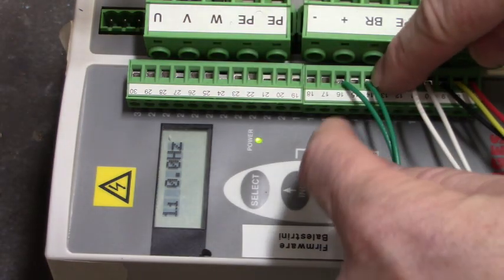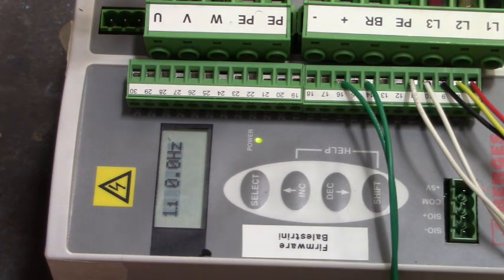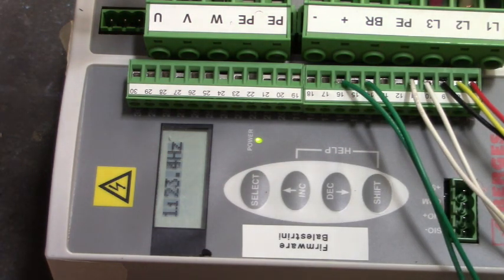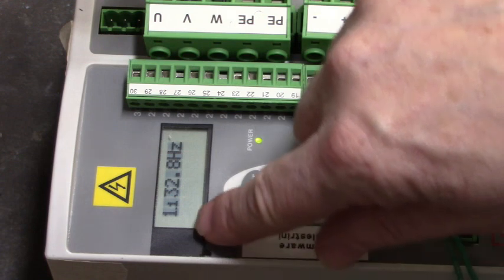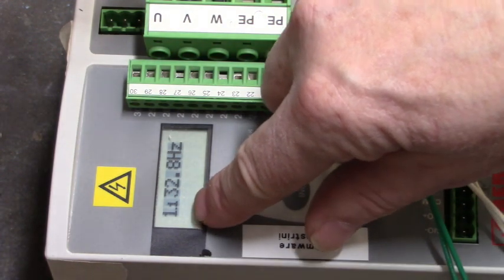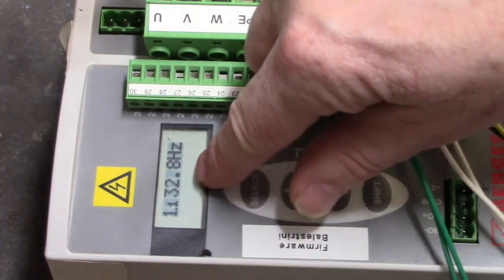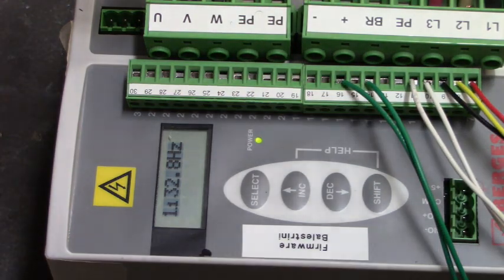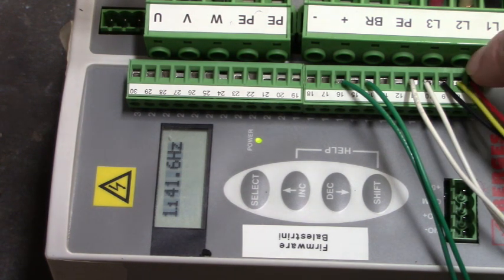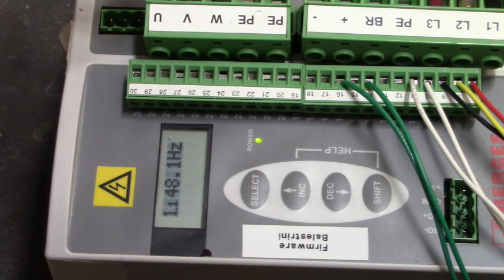I'm going to close the switch on terminals 14 and 16 to run forward. And you can see now our drive displays 1.1 32.8 hertz. And we can change that frequency by varying the voltage on pin 8 with the potentiometer. There we go. Look how easy that was.